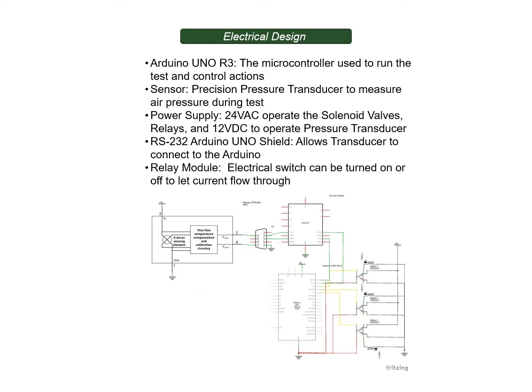The Arduino Uno is the microcontroller that is used to run the test and control the solenoid valves and pressure transducer. An RS-232 Arduino shield is connected to the Arduino to allow the connection to the pressure transducer. We are using a precision pressure transducer to measure air pressure during the test. It is powered with a 12-volt DC power supply. A 24-volt AC power supply is used to operate the solenoid valves, with relays connected to them to convert small electrical stimuli into larger currents. They can be connected to any digital pins on the Arduino.